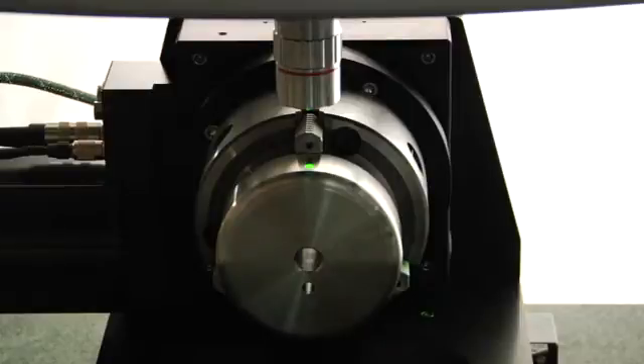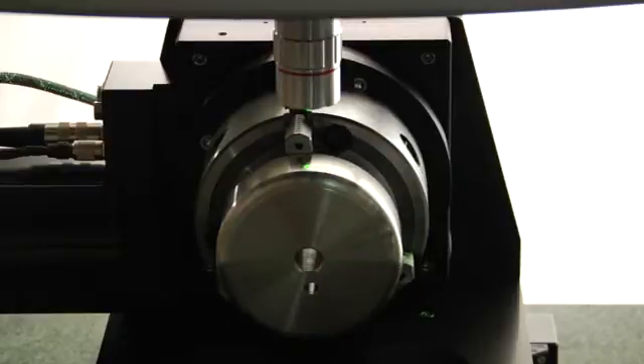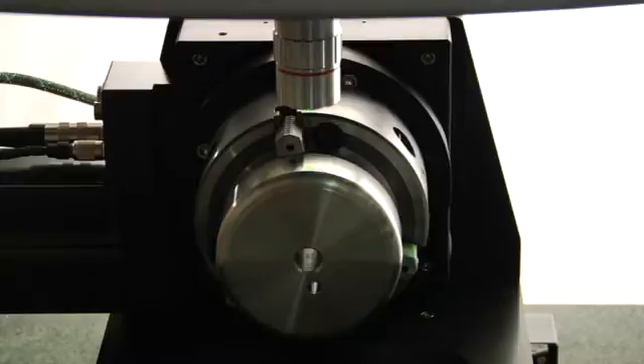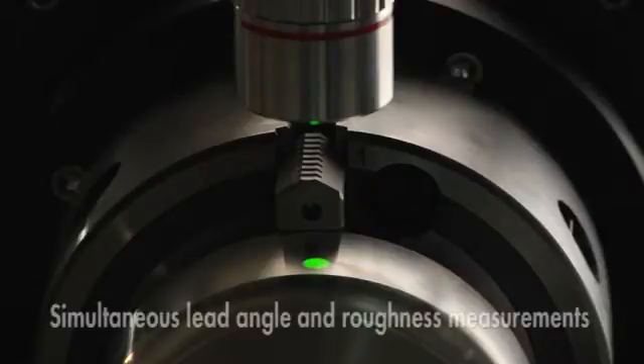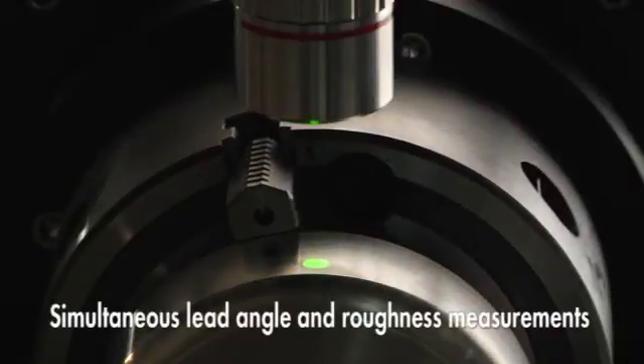During a single measurement routine, NP-FLEX LA calculates the radius of the cylinder and the angular power spectral density (PSD) with respect to a common reference at each location along the shaft. This self-referencing method removes the influences of camera, stage, chuck, and part alignment from the calculation, reports global lead angle and both standard surface textures.